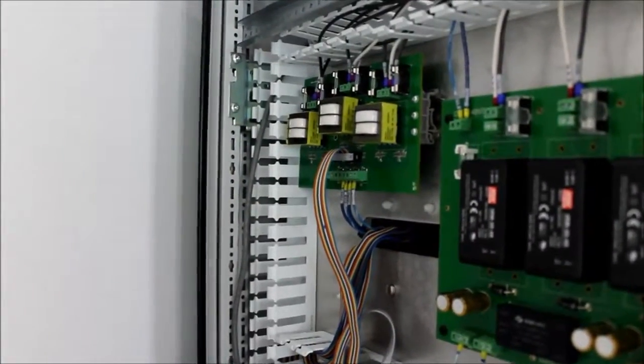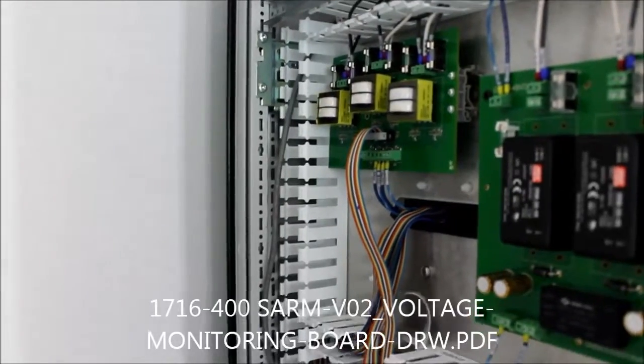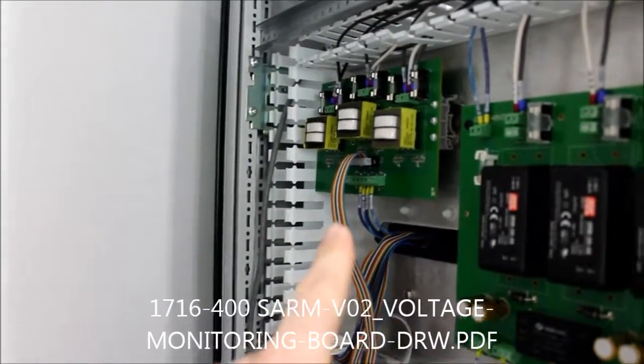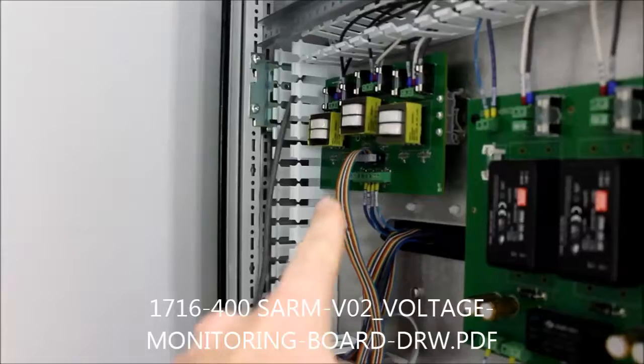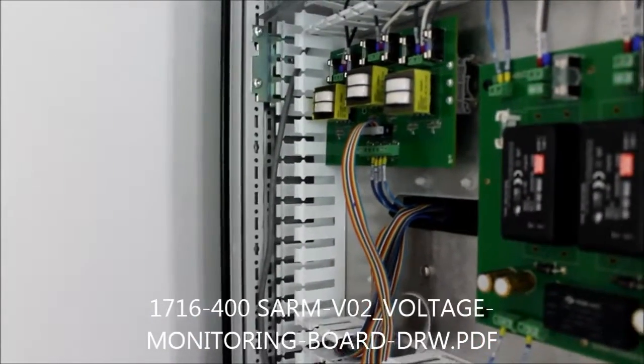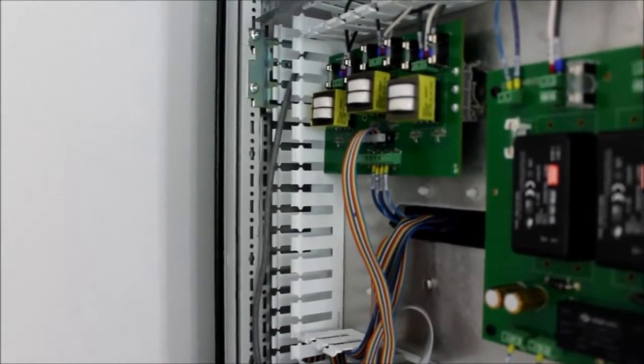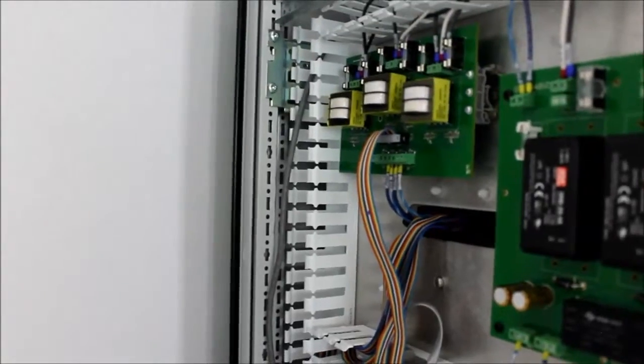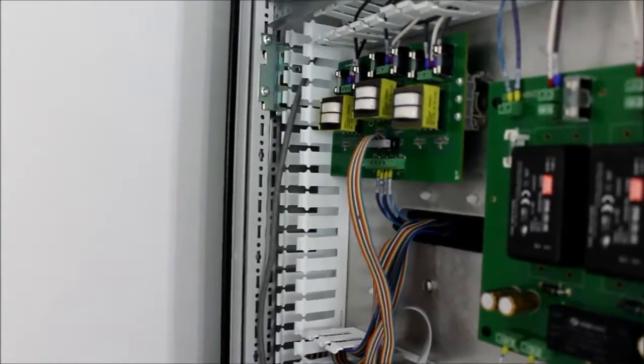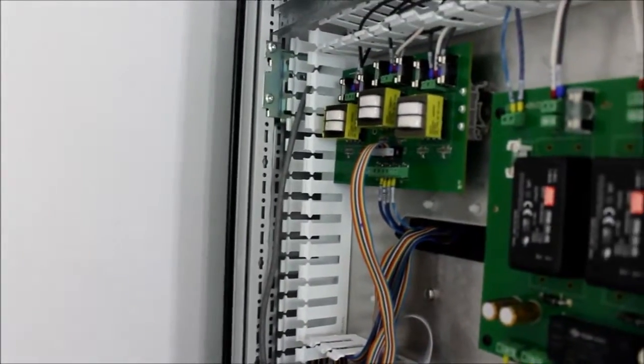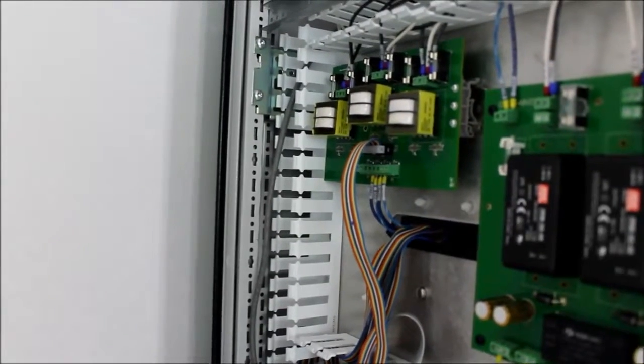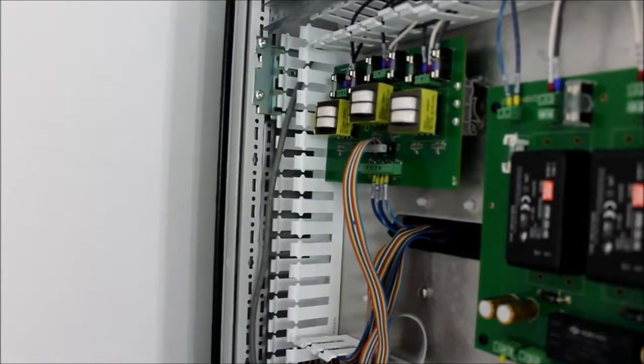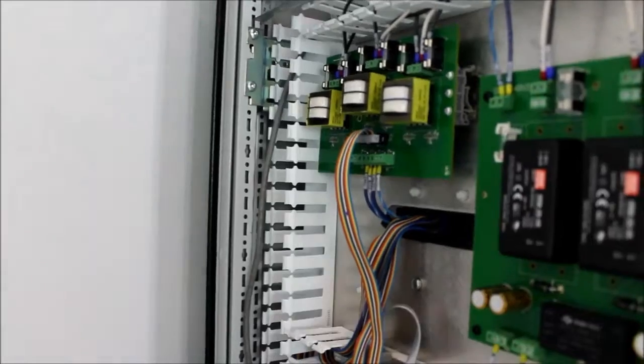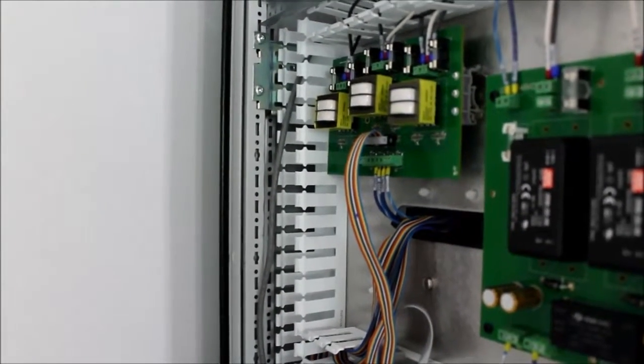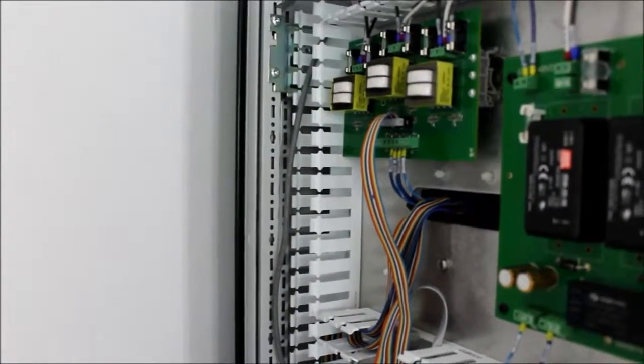Also on this side of the enclosure is the voltage monitoring board here. The voltage monitoring board can accept 4 DC inputs. In this system we use 2, and 3 AC split phase inputs, so it knows the voltage conditions for the grid, the output of the energy system, and the output of a secondary generation system such as a generator.